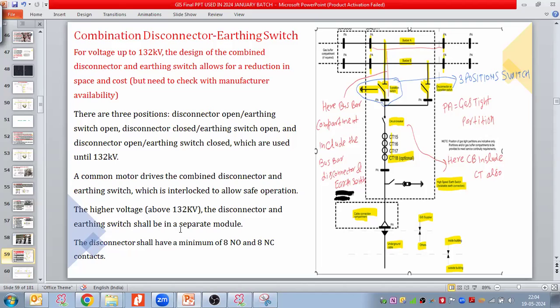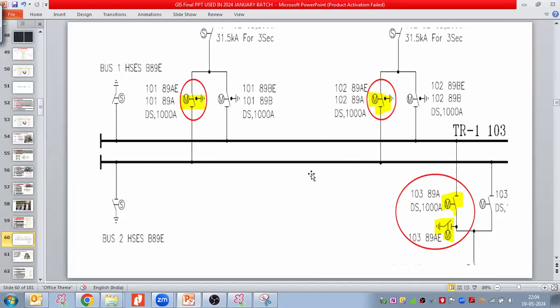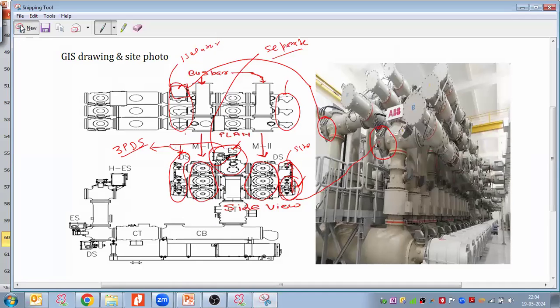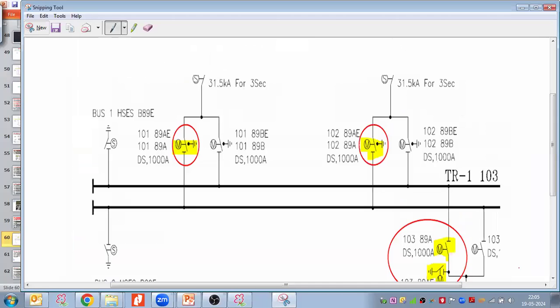So for higher voltage levels, the disconnectors and earthing switch shall be separate modules. The disconnectors shall have a minimum 8NO and 8NC contacts for signaling purposes. If we are taking a 3PDS arrangement, the SLD will be according to that arrangement, so when you prepare the SLD, make sure what arrangement you are taking. If you are taking the 3PDS arrangement for the disconnectors and earthing switch, your SLD will look like this. This is the combined arrangement.